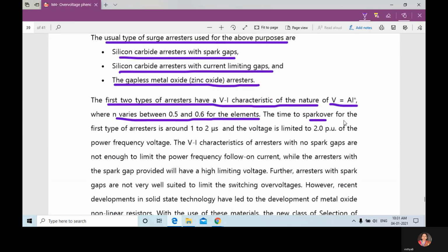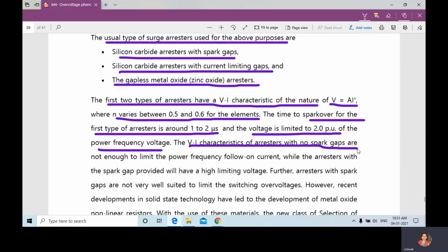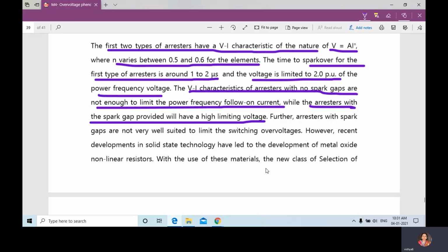The time to spark for the first type of arrestor is about 1 to 2 microseconds, and the voltage is limited to 2 pu of the power frequency voltage. The next is the VI characteristics of the arrestor with no spark gap. Arrestors with no spark gap are not enough to limit the power frequency follow-on current, while the arrestor with spark gap provided will have a high limiting voltage.